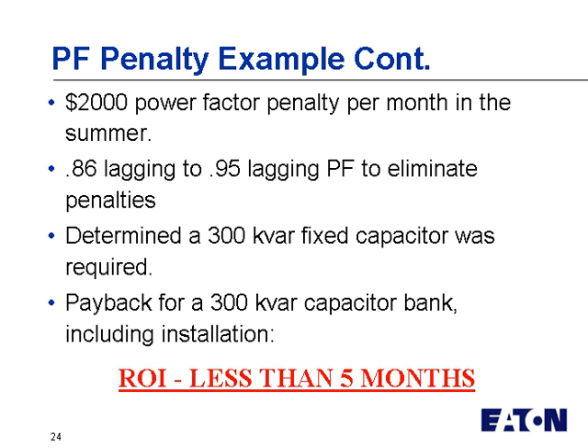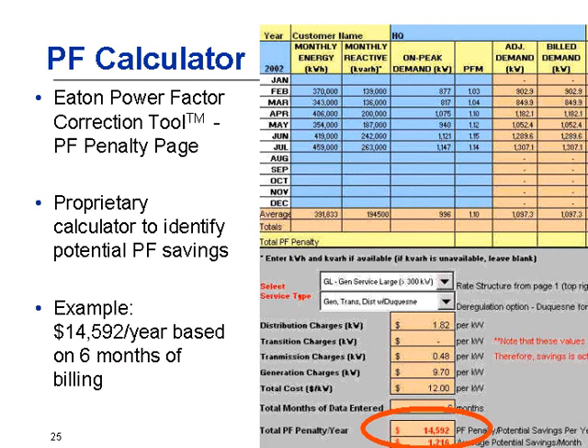This is more detail on that example, but it turns out that we applied a 300 kVAR fixed capacitor bank, and the return on investment was less than 5 months. Almost like a no-brainer, but we didn't realize the penalty was there. And again, the reason is because the people that pay the bill don't necessarily look at the bill or don't necessarily analyze the bill as we would.